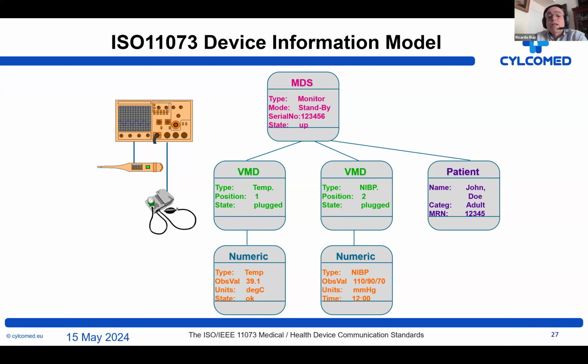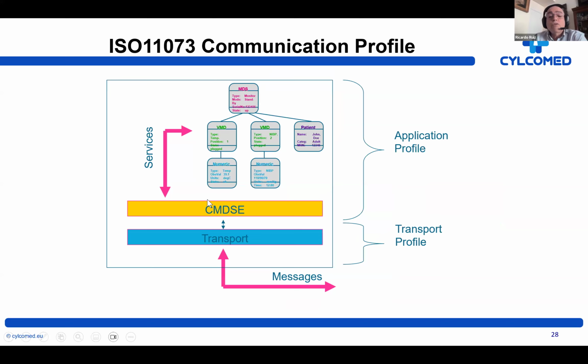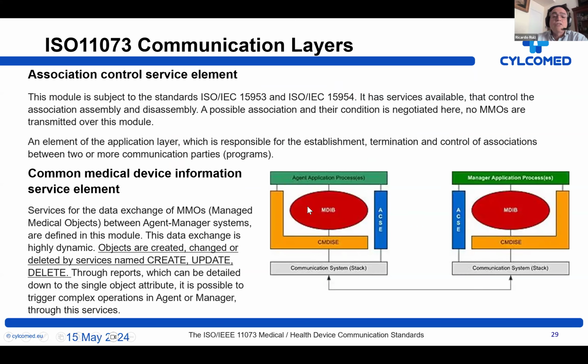And essentially, as I said before, it is continually updated by the monitor itself, and there are means to transfer this information through services, through the CMDISE service model, that will be able to have a look at each object and to create, for example, what is called a scanner. The scanner will be looking at every object, and whenever there is a change, it will be transmitting this information through the transport layer by a message that will be reaching the manager. So the manager has a copy at all times of the information that is available in every agent.